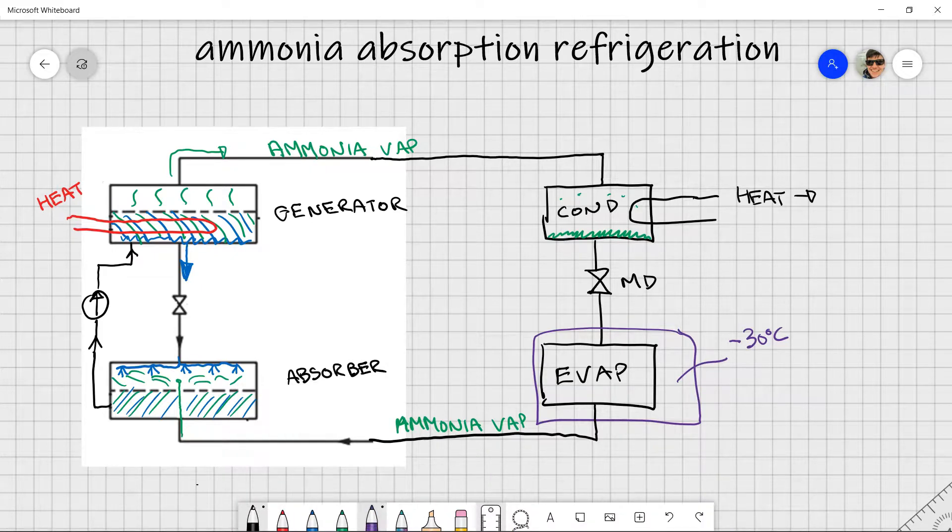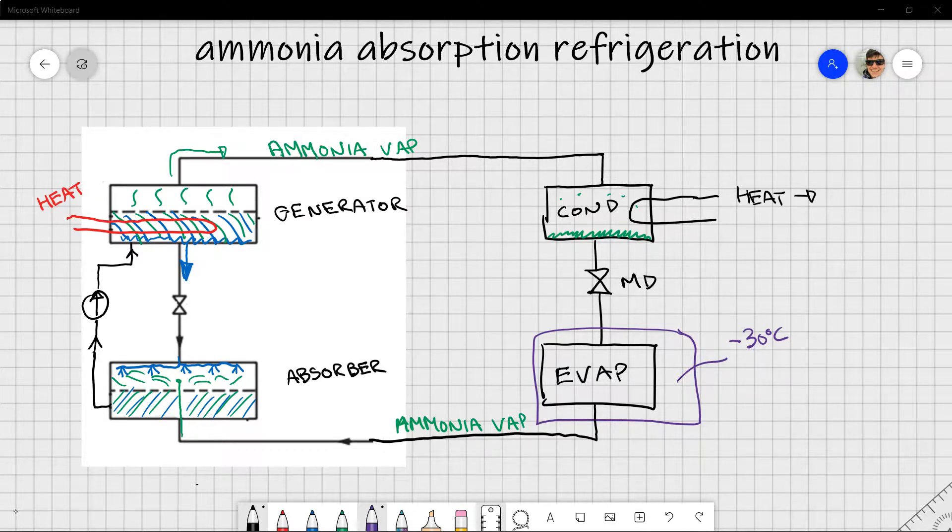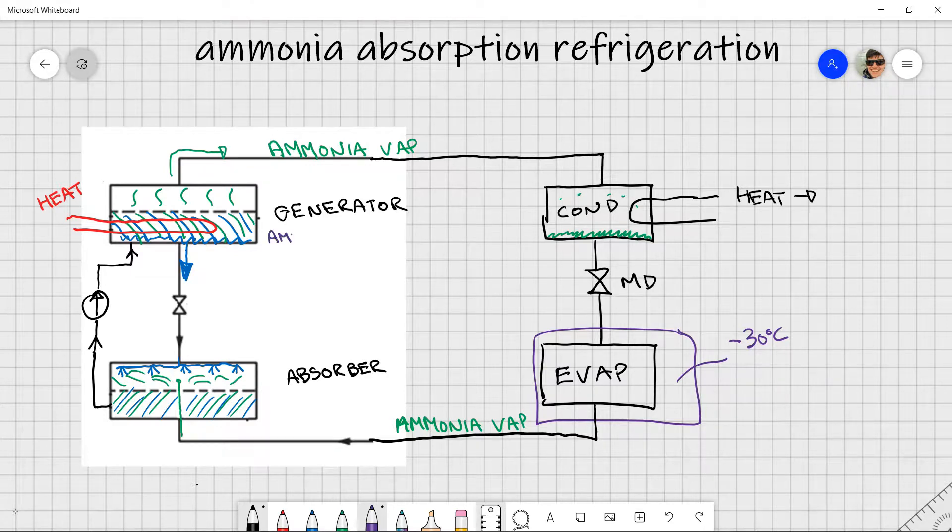And so we have some terms for those water mixtures. So up at the very top we have our lowest concentration of ammonia, which is essentially a low concentration of ammonia and that's what we would consider to be a weak solution and we call that a weak aqua solution. And down at the bottom here in the absorber where we have a higher concentration of ammonia we would consider that to be a strong aqua solution. So we have four new terms: we have our generator, we have our absorber, and we have our weak aqua and our strong aqua.